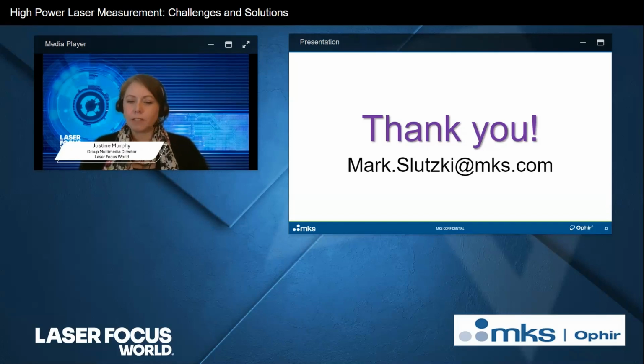All right. The sensor specification sheet states that power accuracy is plus or minus 5%, or 3% for lower power sensors. What exactly does that mean? Okay, so the power, all right, this is a big topic, but basically the power accuracy of plus minus 5%, let's say, refers to the absolute uncertainty of the measured value with reference to NIST. All of the calibrations are traceable to NIST. So for example, if you have a 1 kilowatt reading, and the sensor's specified accuracy is plus minus 5%, that means that the actual true power value would be somewhere between 0.95 kilowatts and 1.05 kilowatts, 5% above or below that 1 kilowatt measurement.